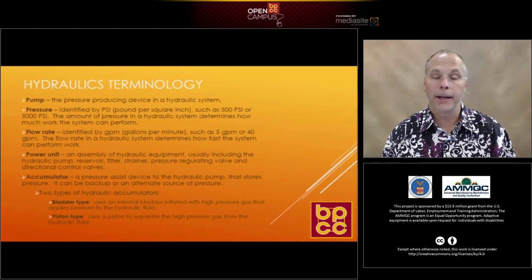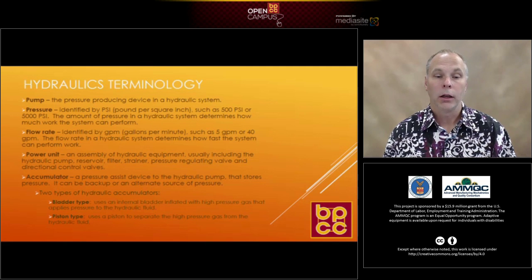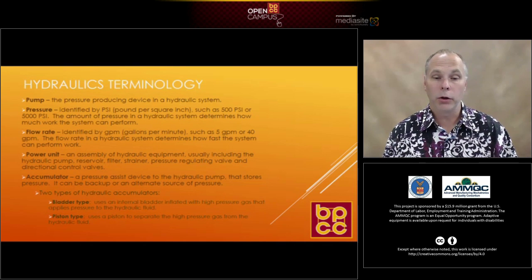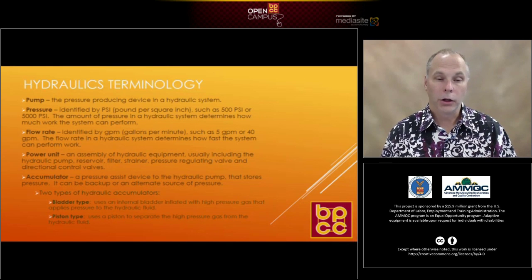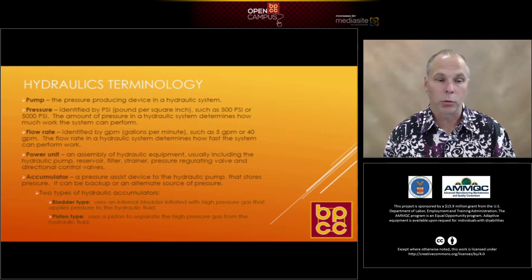If you're utilizing a certain type of actuator, such as a cylinder, and you can transfer the fluid very quickly — say at 40 or 50 gallons per minute — then you're pushing a lot of fluid and therefore you can move that cylinder really fast. You can use different types of flow control valves to adjust that, and pressure control valves to adjust your pressure to make sure you're not over-pressurizing the system.